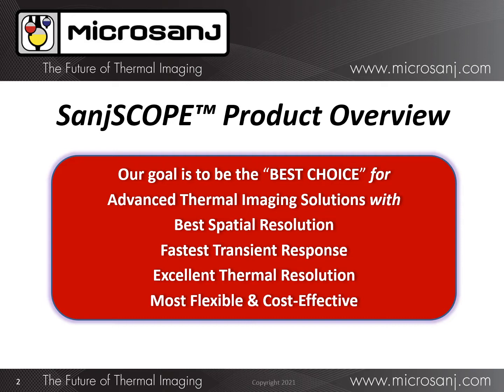Most of our systems also support infrared emission thermography to take advantage of the thermal sensitivity this imaging technique offers. This enables the detection of very low power hotspots or other circuit-induced thermal anomalies that may contribute to an early device failure.